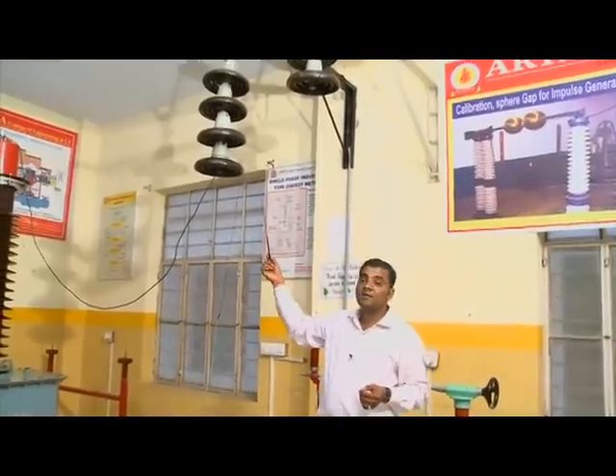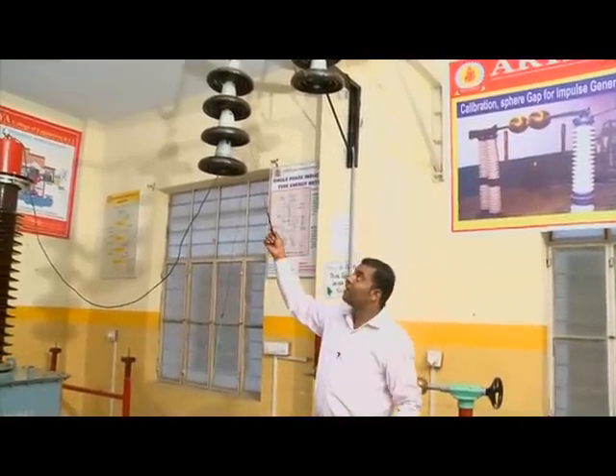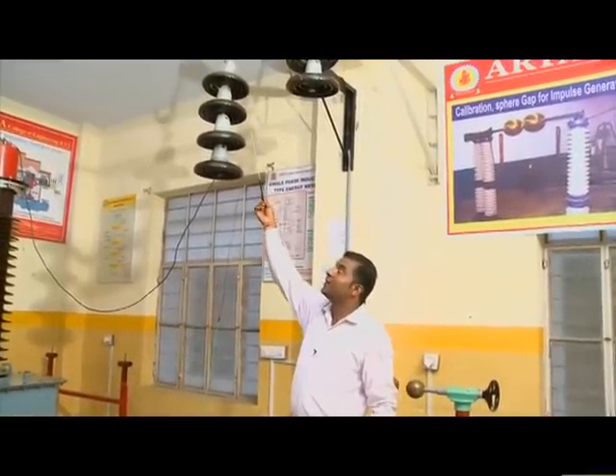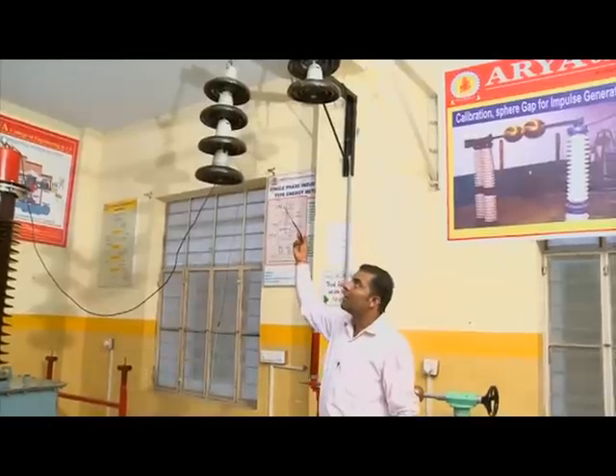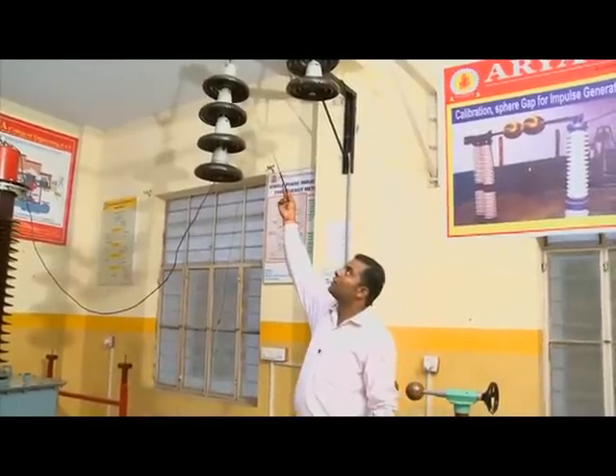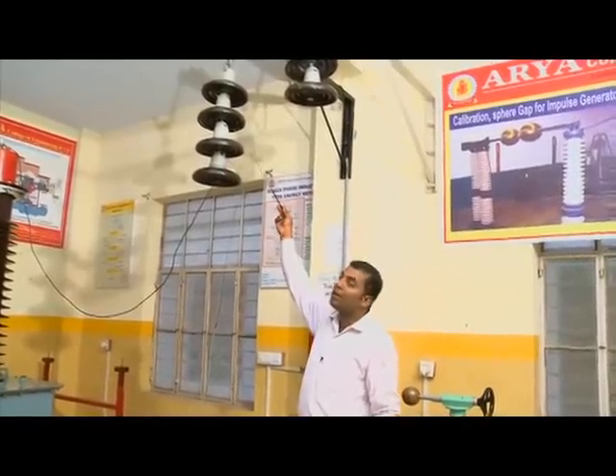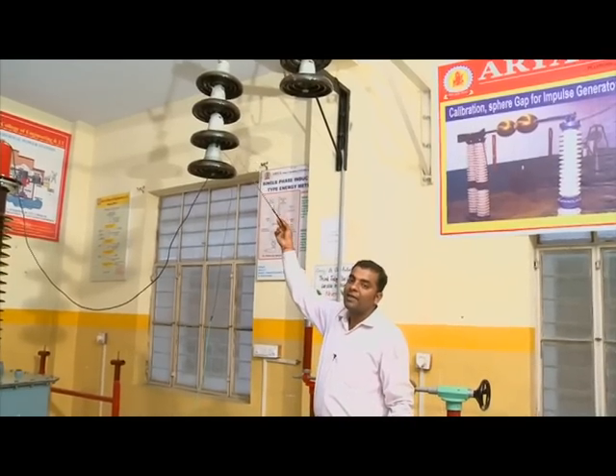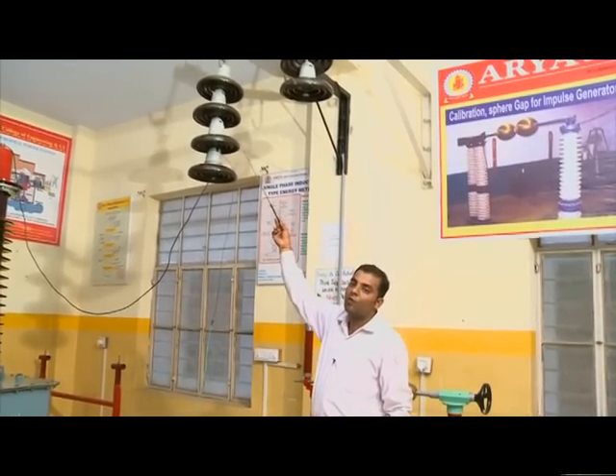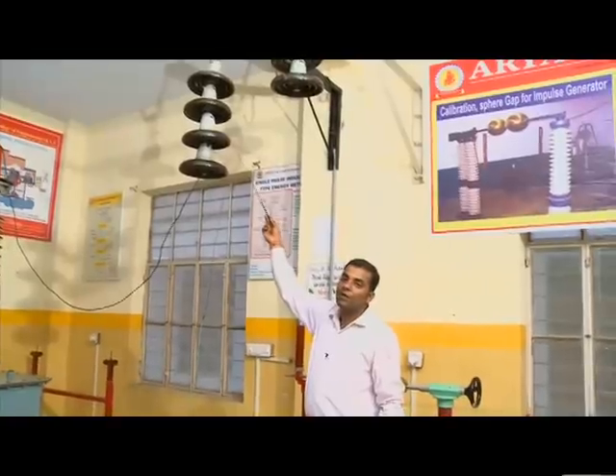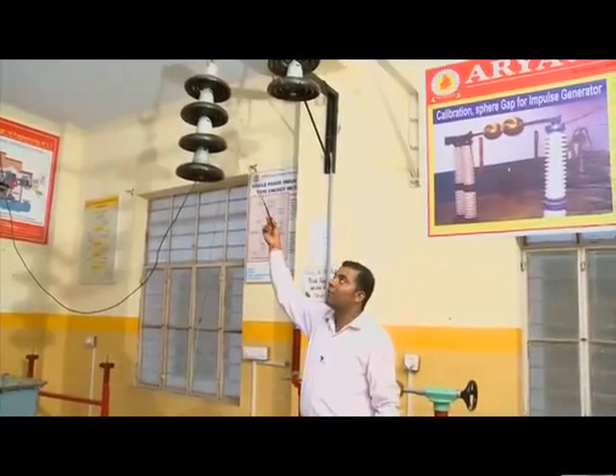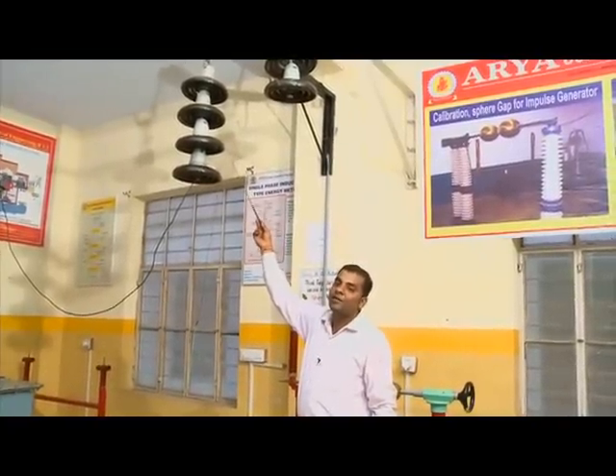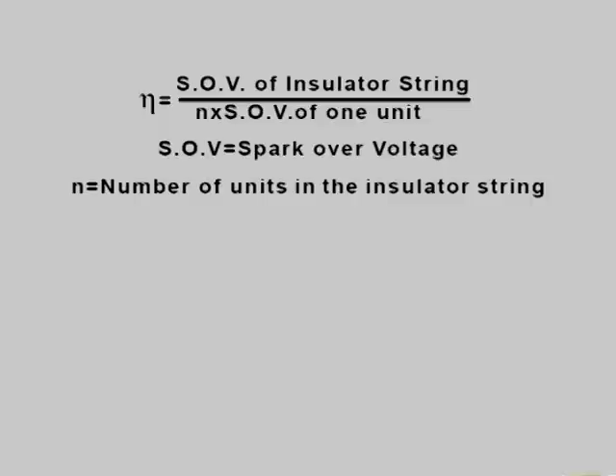Again, we will repeat the same process with the second, third and fourth units of the insulator string. We will connect the second, third and fourth units of the insulator string and observe the three values of spark over voltage, and substitute these values of spark over voltage in the formula to calculate the efficiency of the insulator string. Now we will calculate the value of efficiency of the insulator string.